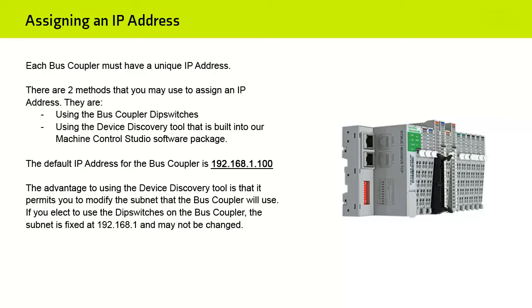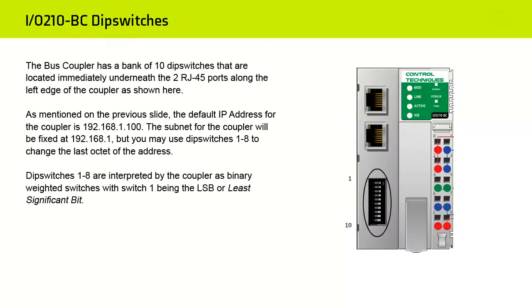The advantage to using the Device Discovery Tool is that it permits you to modify the subnet that the Bus Coupler will use. If you elect to use the DIP switches on the Bus Coupler, the subnet is fixed at 192.168.1 and may not be changed. The Bus Coupler has a bank of 10 DIP switches that are located immediately underneath the two RJ45 ports along the left edge of the Coupler as shown here.